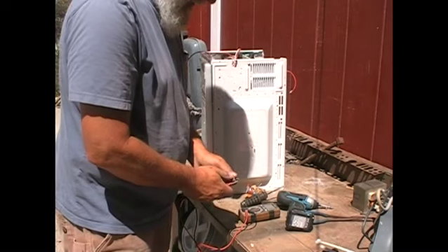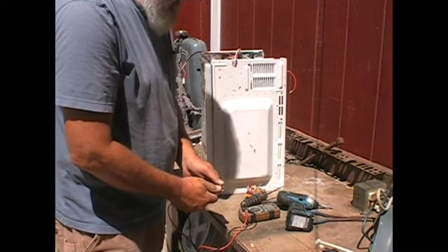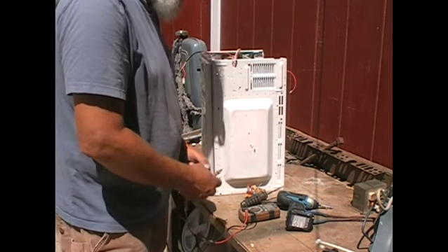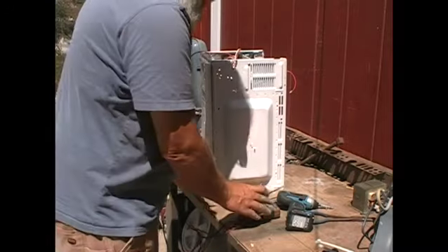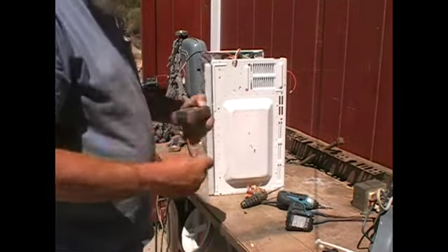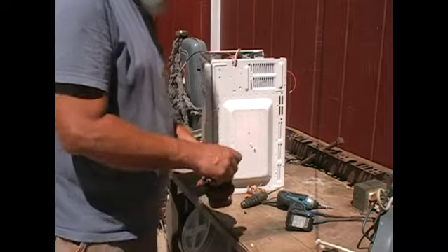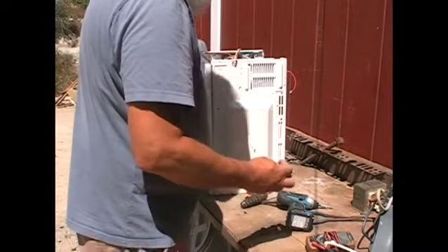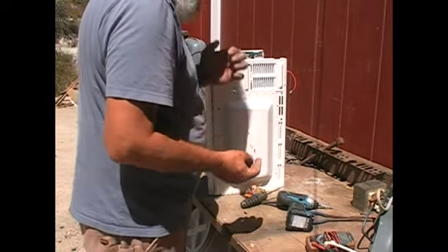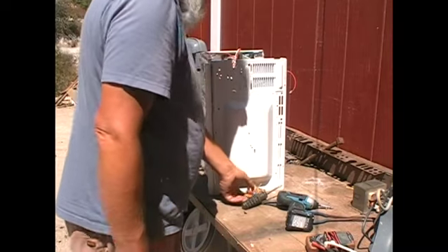Okay, we're going to go across our fuse here, and it gives us a reading of 0 ohms. That means the fuse is good - the element across it inside is still intact, conducting the full voltage across. So that wasn't the problem.